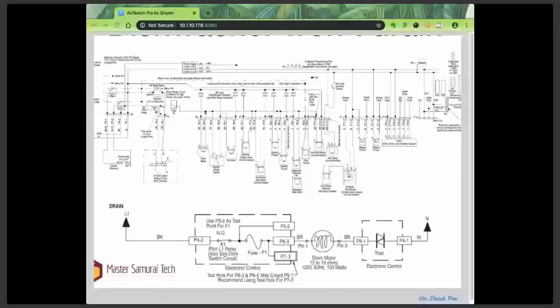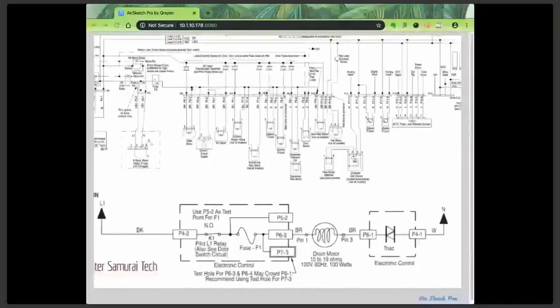So what if I wanted to check amps on this drain pump, the preferred test for any skilled tech? Can I do that? They didn't give me amps. Well, yes, they actually did. They gave me watts, and they gave me a power supply. So I use P equals I times E again, like we did before, and I can calculate what the amps should be. So in this case, another case of amps being an implicit specification. So what would my expected amp reading be?